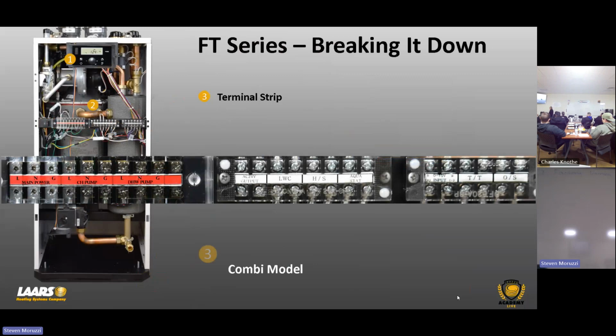This is showing the combi model. And so line voltage coming in on your first 3 terminals. You also have the central heat pump and a DHW pump, okay? And then your terminals here, we give you a 24 volts. There was another gentleman that's sitting over here earlier. We give you 24 volts for the external low water cutoff, all right? And then you'll have your additional low water cutoff terminals here for that, okay? That only has a 2.5 amp fuse on it as well, all right? So that's strictly to power that low water cutoff, all right?